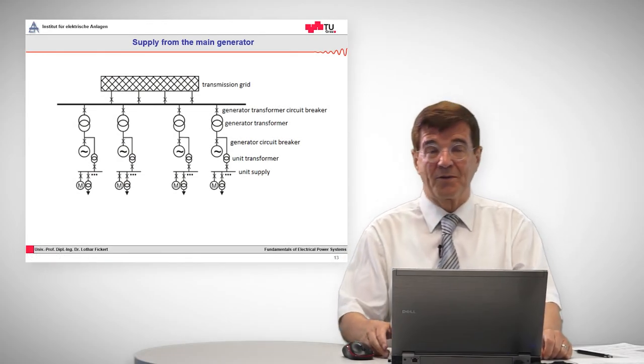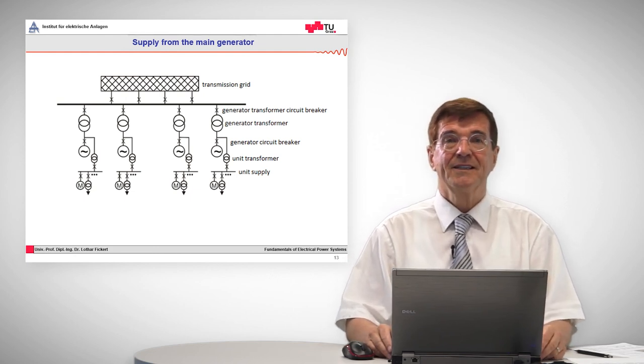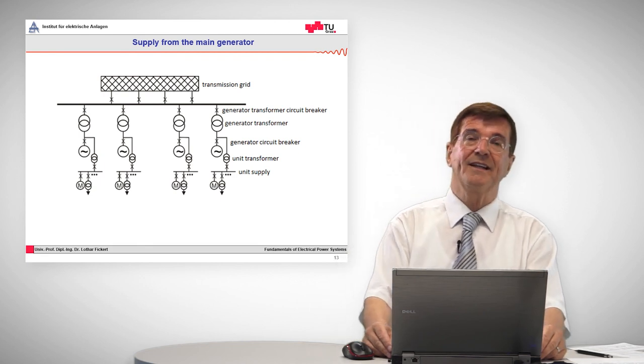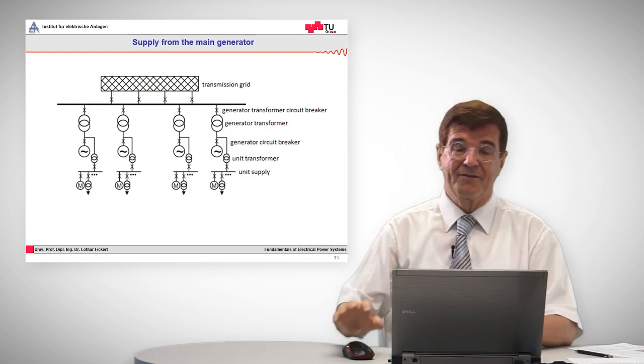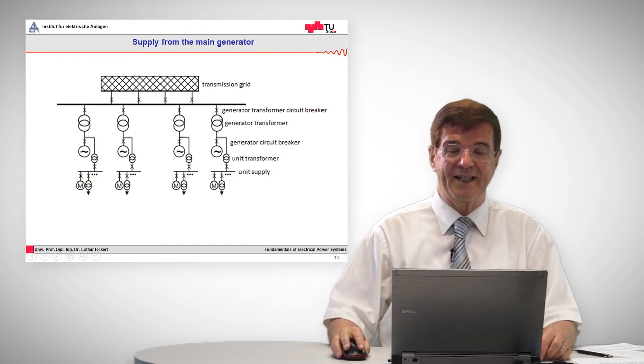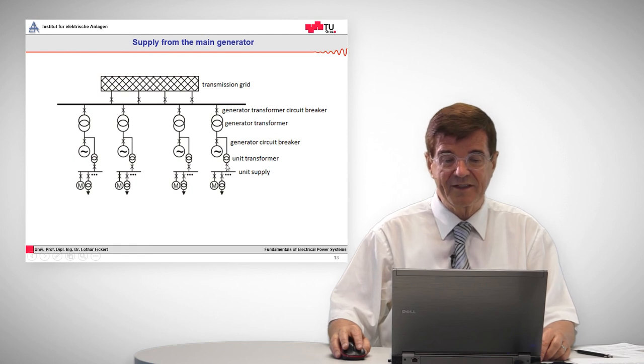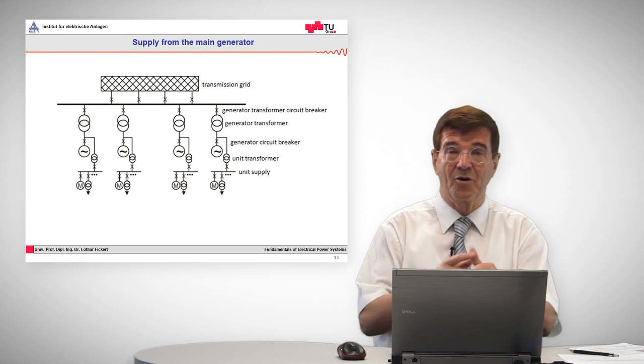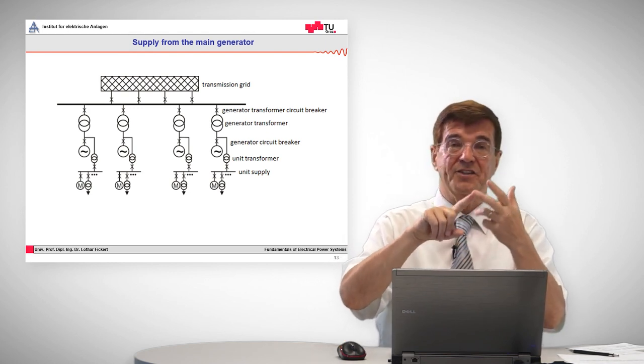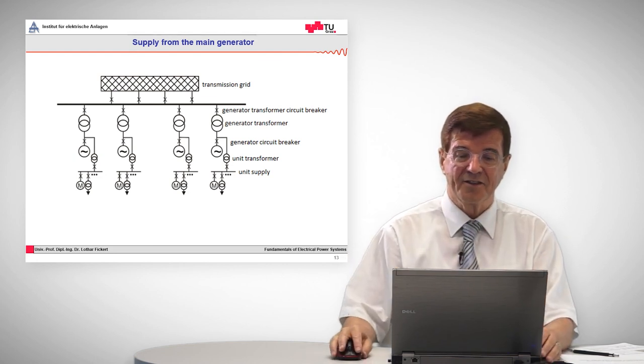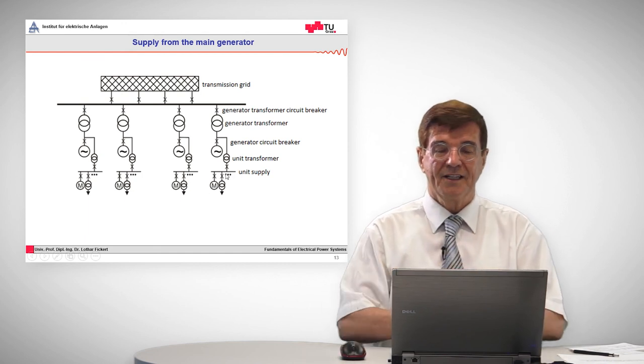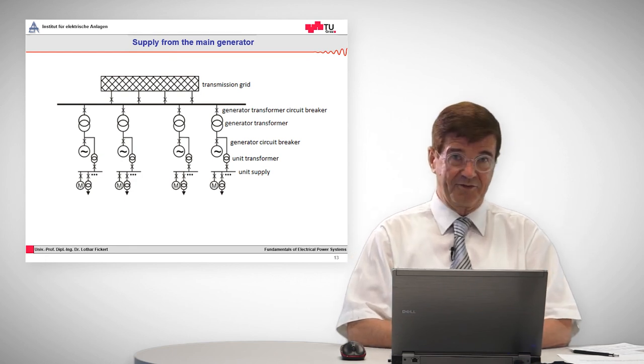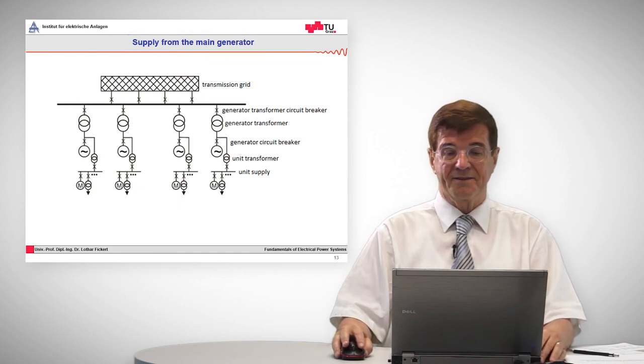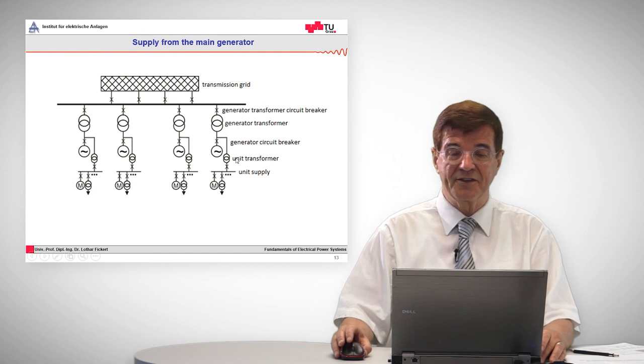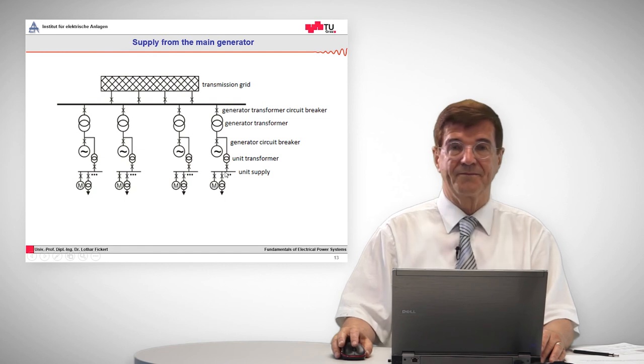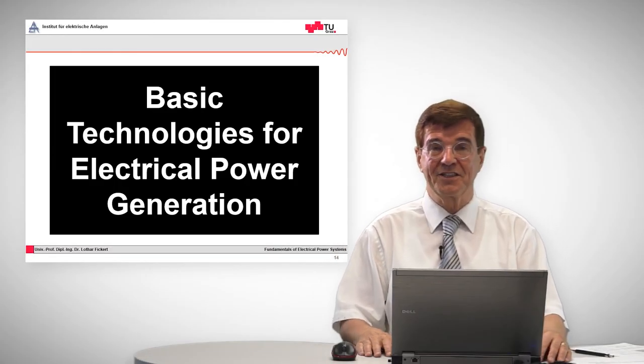The last point, when it comes to power plants operated through, for example, biogas and biomass, is that it is essential to supply the auxiliary services directly at the root where the energy is generated. As we can see here, we have the generator, and the generator, before it releases the energy into the grid, is also used to produce some electrical power for the so-called unit supply. The unit supply is lube oil pumps, ventilators, protection and control devices, emergency lighting, etc. These units are needed just to sustain the operation, and they are also needed if you want to have islanded operation, which is basically possible. This unit supply is fed from the generator through the unit transformer, and that is essential to keep the unit running. So this was the chapter Basic Technologies for Electrical Power Generation.